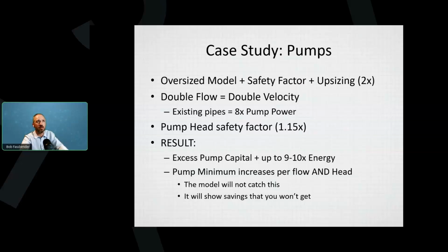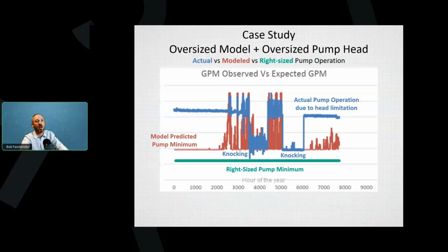And so I'm going to go through the actual data right here. I'll try to be quick about it. So we have the actual versus the model versus what the right size pump would be. And in green at the bottom, that's the right size pump minimum if they had sized the model correctly. In red, that's what the model predicted. You can see most of the time it spends at minimum stop. In blue is what actually happened. And you can see that the pump spends most of its time at a much higher flow rate than it's supposed to. And they tried to lower the flow rate to the minimum stop, and every time they did, they had pump knocking. And that's because the system was designed for a much higher flow rate than needed.